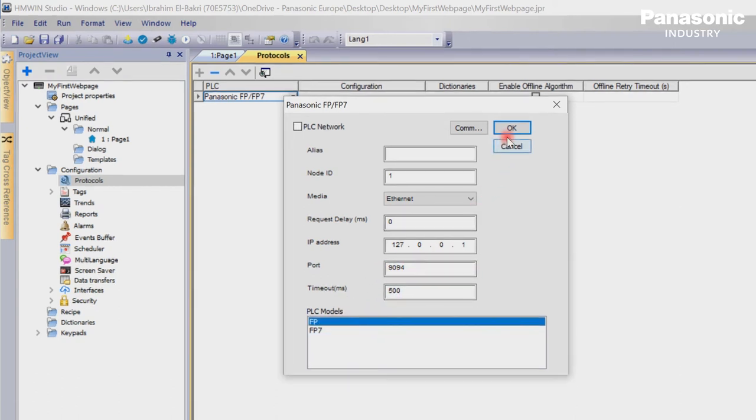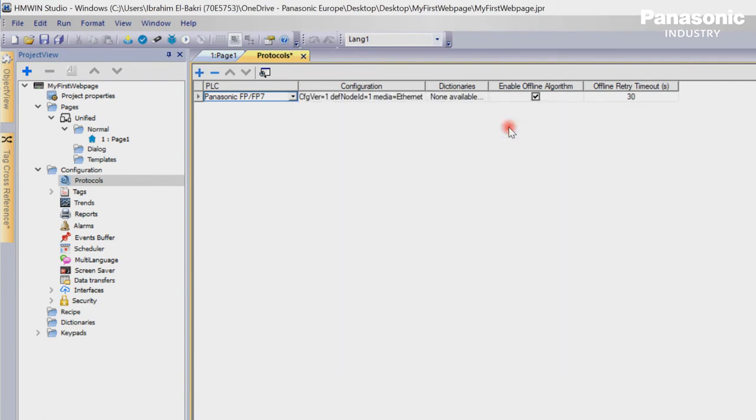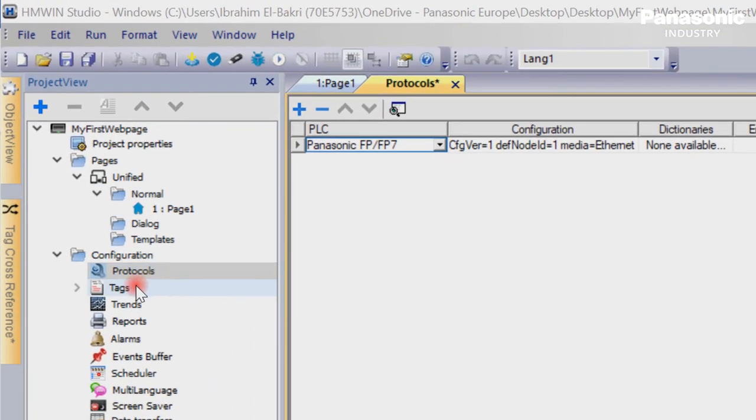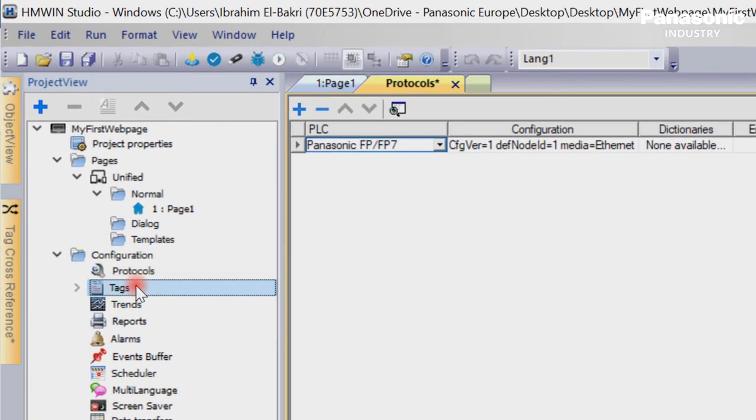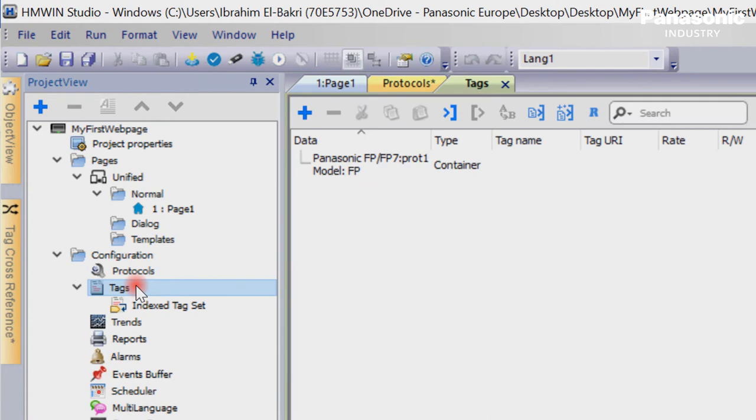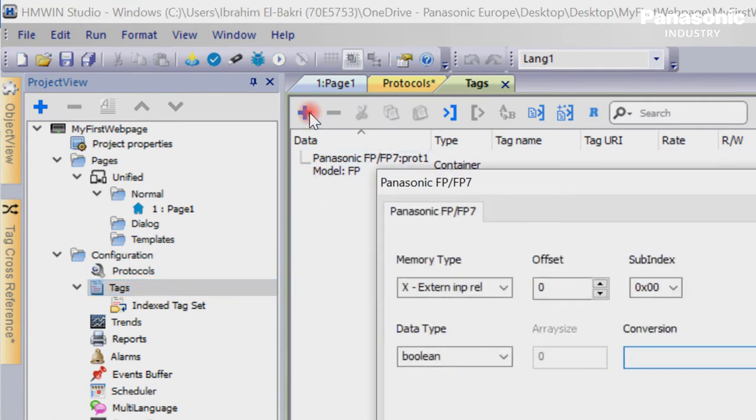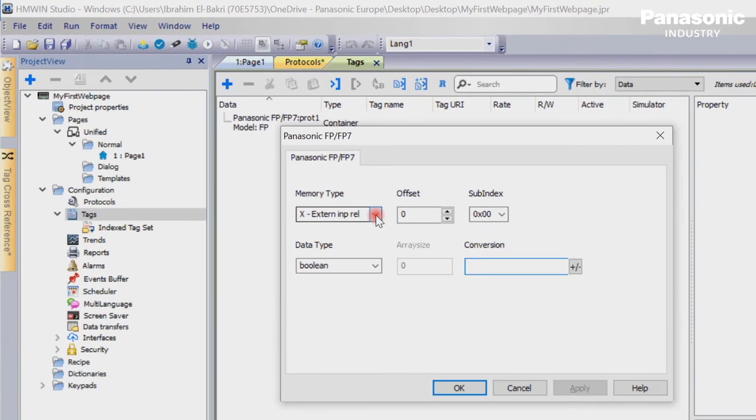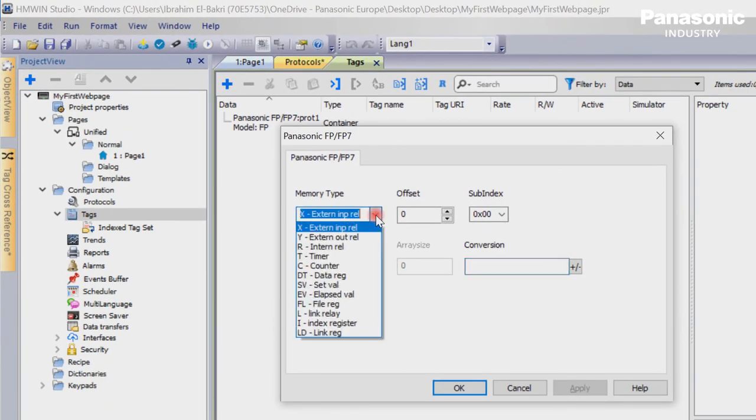Now the communication driver is ready and we can prepare the so-called tags. We double-click in the configuration folder on tags. In the tags window we press the button Plus. We create a tag with the according PLC register which we defined already in our PLC program.